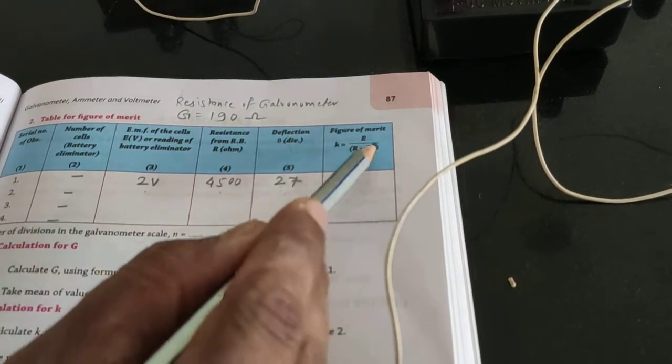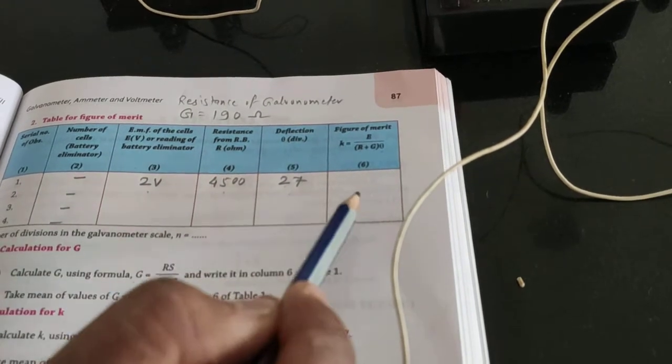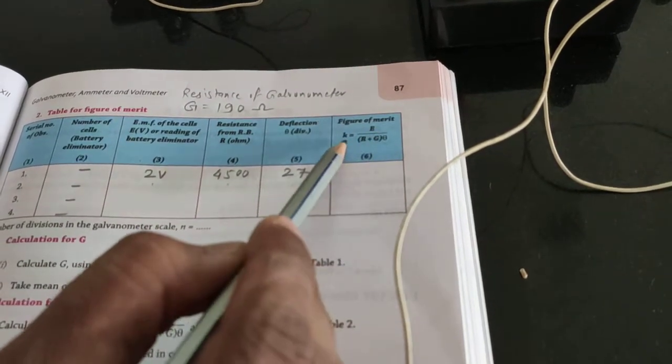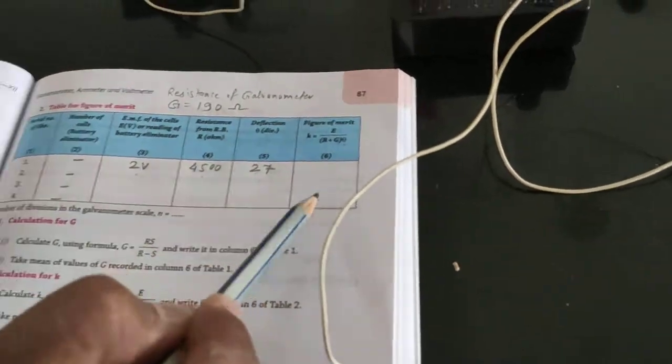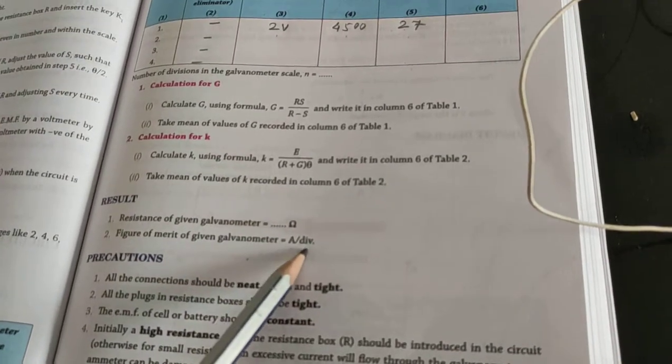By taking all the different readings, approximately 4-5 readings, we will take that - I will send you in a PDF form. You will get the different values or approximately same values of figure of merit. Again we will take mean value of that, and we can write the figure of merit value in ampere per division.